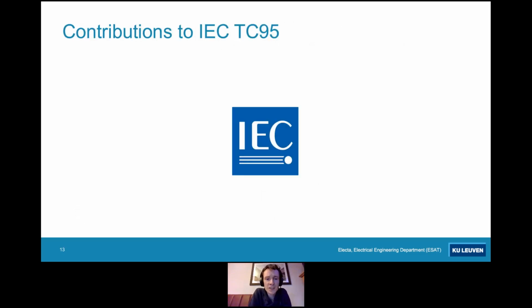Finally, the HVDC grid should not be built by a single vendor, so there should be interoperability between multiple vendors, and that means that standardization is required. The IEC, the International Electrotechnical Commission, has acknowledged the need for standardization in HVDC grids, and they have created two ad hoc working groups, one of which is on HVDC grid protection. With colleagues within KU Leuven and Energyville, we are actively contributing to one of these ad hoc standardization groups.